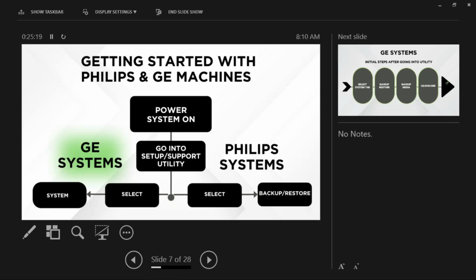For this particular one, it gives you a little bit of information here, like the last time it was backed up. And the 2 things you want to make sure you back up on this particular system are user-defined configuration and service configuration. If you come into the GE systems and you find out that you only have the user-defined configuration backed up, you're not going to have the options of the system.